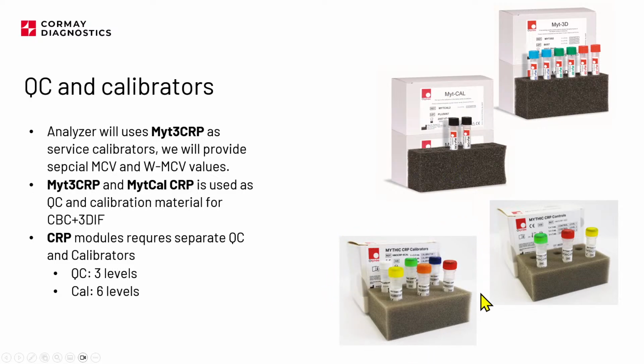And for calibrators, for the CRP module, as you can see, there are 6 different vials. So it's level 1, 2, 3, 4, 5, 6, right? And actually on the analyzer, you will have calibrator 1, 2, 3, 4, 5, 6. And for the CRP control, there are only 3 levels, right? Low, normal, high, something like that. I don't remember what the color codings on the caps are, but it says level 1, 2, 3, something like that on the vial.